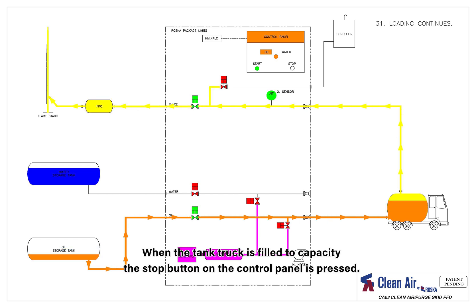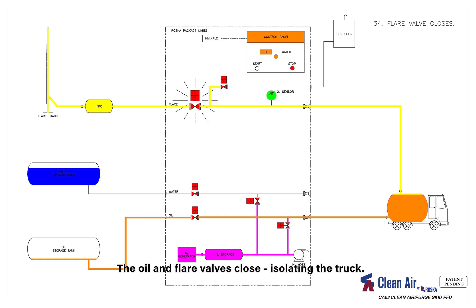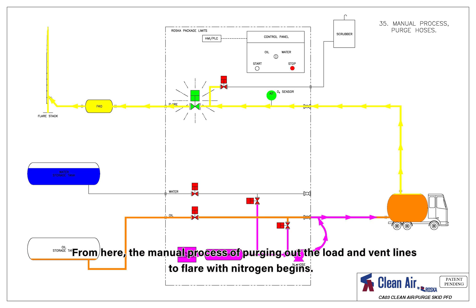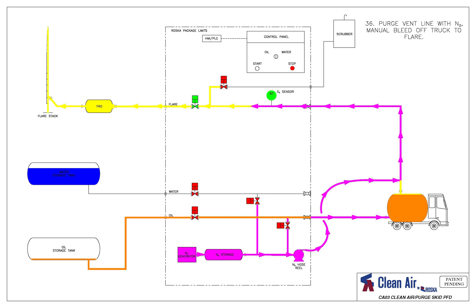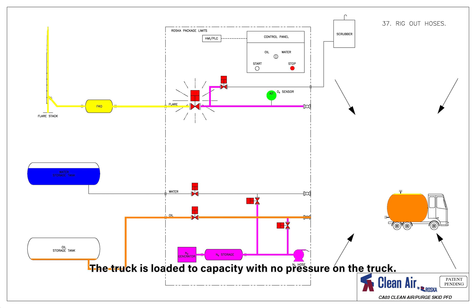When the tank truck is filled to capacity, the stop button on the control panel is pressed. The oil and flare valves close, isolating the truck. From here, the manual process of purging out the load and vent lines to flare with nitrogen begins. After this, the flare valve is closed and the tank truck is rigged out. The truck is loaded to capacity with no pressure on the truck.